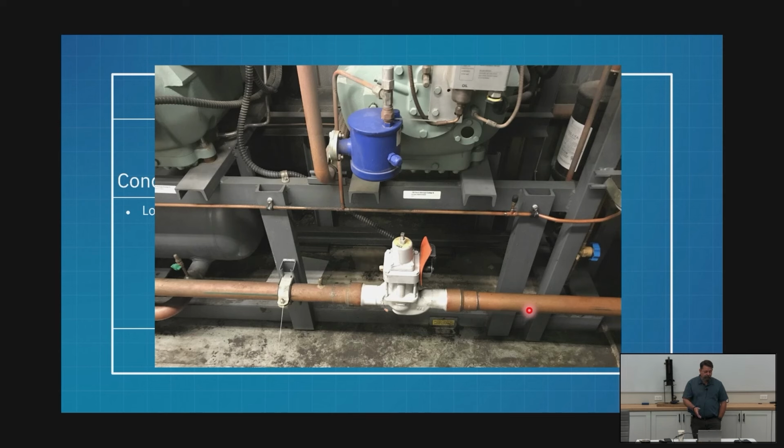If I know my target, I go to my stop and turn it 3.5 turns, 3.75 turns. Do you think there's ever a scenario where we're going to run into conditions that affect us in the summertime or in the wintertime? It'd have to be grossly off. If it's supposed to be 150 in the summer, you're running 250? It'd have to be extremely far off. But it could have happened. Sure, that screw will just keep on turning.